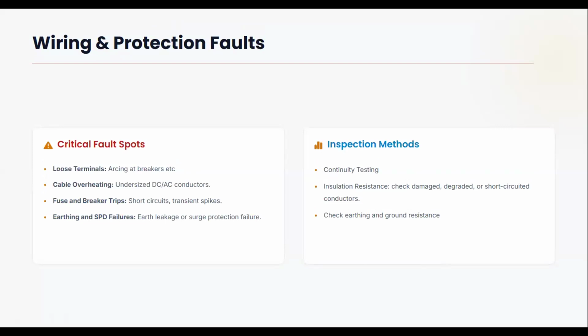Insulation resistance: check for damaged, degraded, or short-circuited conductors. Yes, conductors can get connected together when there is overheating caused by a short circuit, which is caused by overload or reverse polarity from the installation.